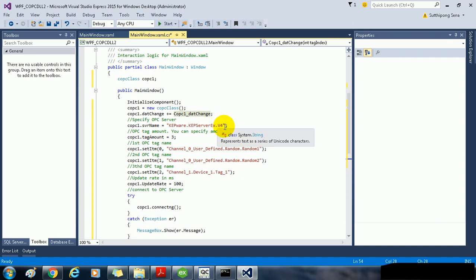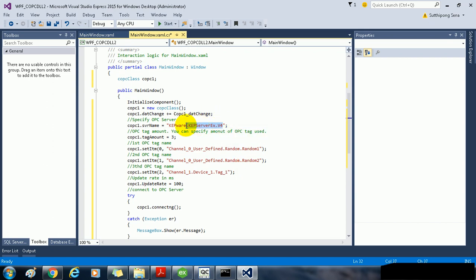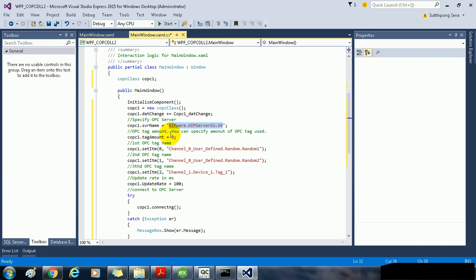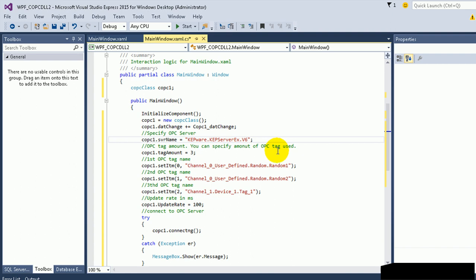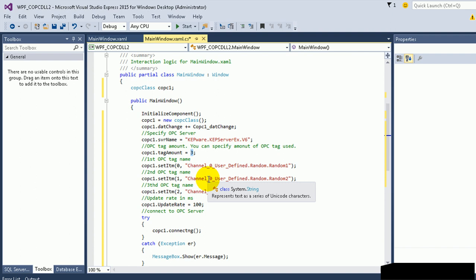Now you have to modify the OPC server name. For example, if you have the Kepware Kepserver EX V6, you have to rename it to V6. And the amount of OPC tag. For example, if you would like to connect to the OPC tag for 100 tags, you need to type 100 here. In this example, I will use 3 tags.